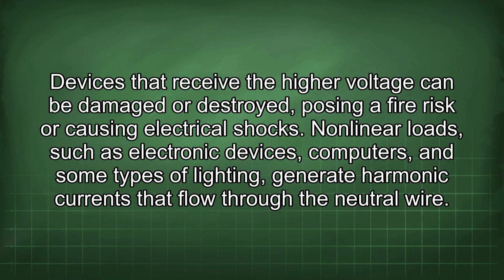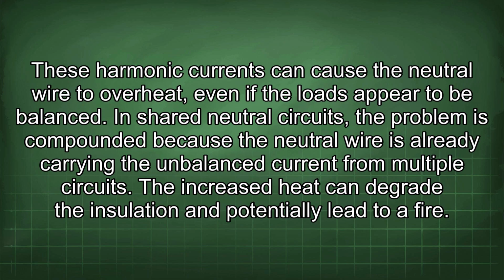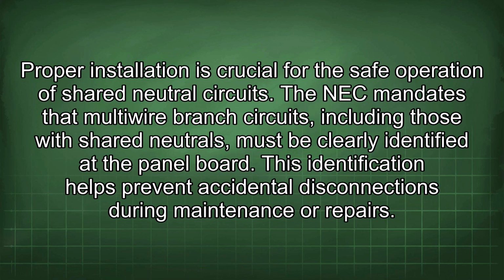Nonlinear loads, such as electronic devices, computers, and some types of lighting, generate harmonic currents that flow through the neutral wire. These harmonic currents can cause the neutral wire to overheat, even if the loads appear to be balanced. In shared neutral circuits, the problem is compounded because the neutral wire is already carrying the unbalanced current for multiple circuits. The increased heat can degrade the insulation and potentially lead to a fire. Proper installation is crucial for the safe operation of shared neutral circuits. The NEC mandates that multi-wire branch circuits, including those with shared neutrals, must be clearly identified at the panel board.